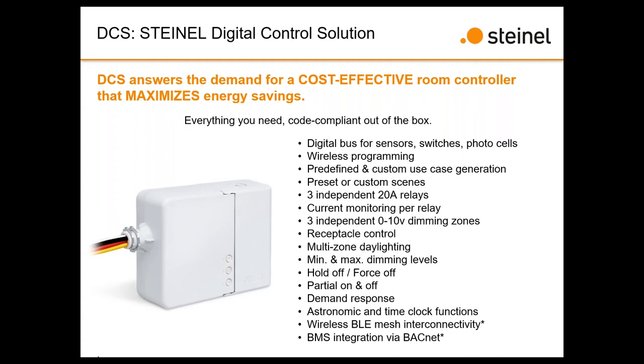Multi-zone daylight harvesting or daylight control. With each of the different zones, you can connect a different photocell, and you can have your own daylight harvesting settings for each of the different zones. Min-max dim levels, hold off, force off, partial on, partial off. And some of the biggies that are unique here: we do have demand response capability built into each of the relays, or excuse me, into the device, and we've got the astronomic and regular time clock functions.